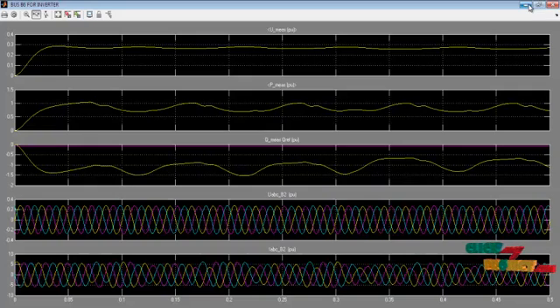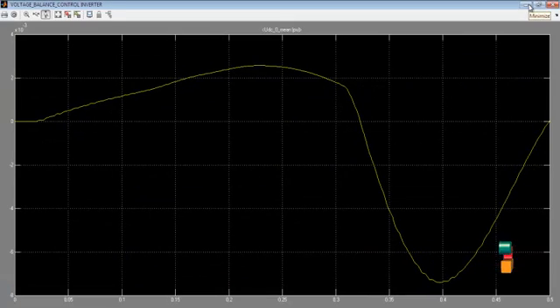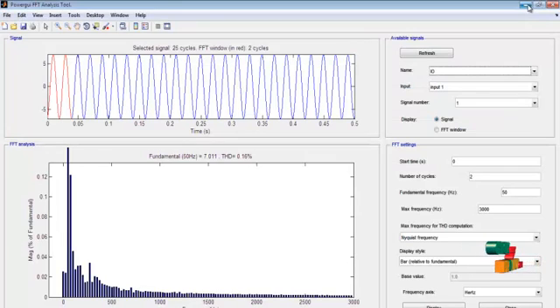Next are the VDC values, next is the filter bus inverter output, and next is the THD value. This window is used to measure the THD value for our output. This is the output current THD, the value is 0.16%. This value is very low compared to other designs.